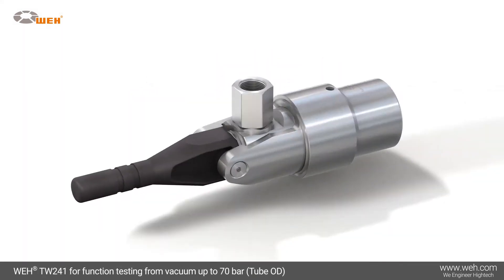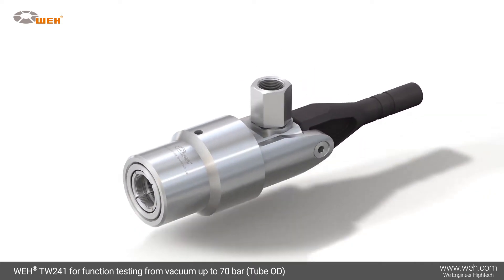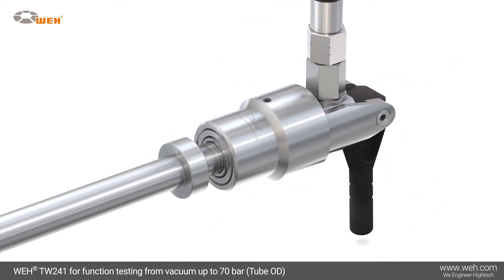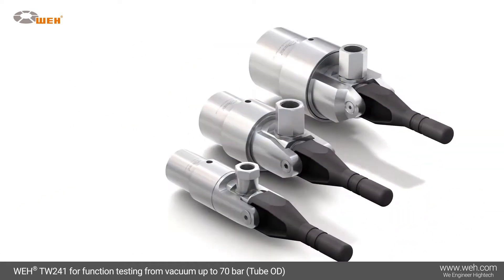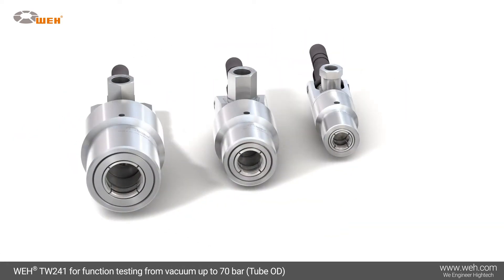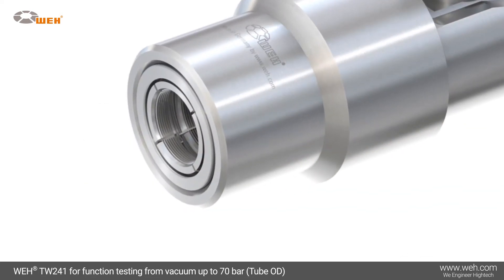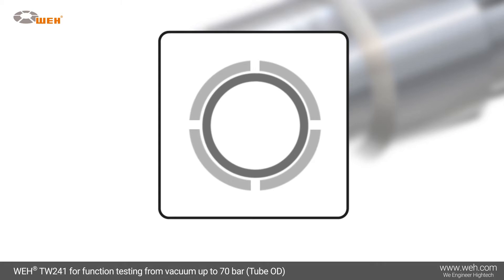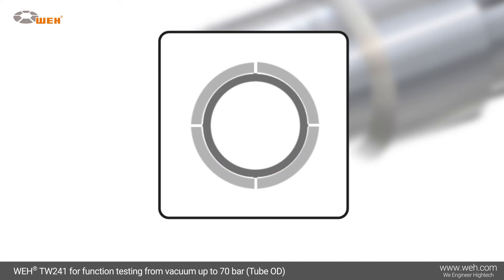The WEH TW241 quick connector enables quick and easy leak testing of straight tubes having an outer diameter of 6.0 to 22.2 millimeters. The connector is available in three body sizes and is suitable for underwater, pressure decay, and vacuum testing with helium. It operates from vacuum up to 70 bar, bridging large tube tolerances of up to plus or minus 0.25 millimeters with no operational adjustment of seals.